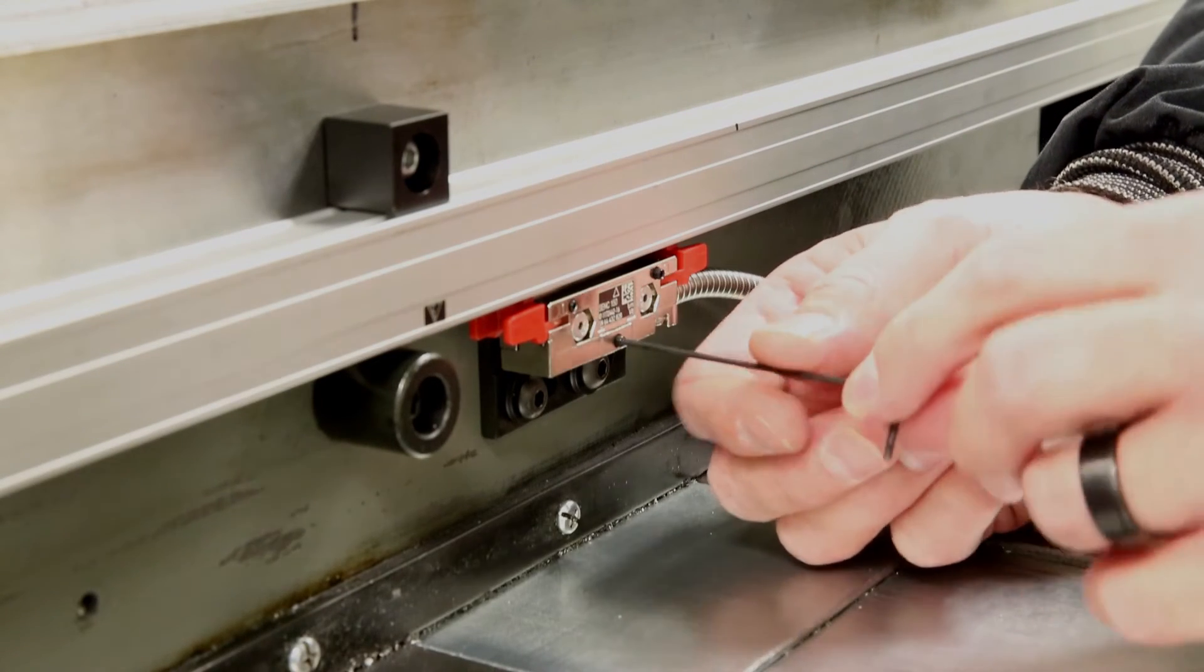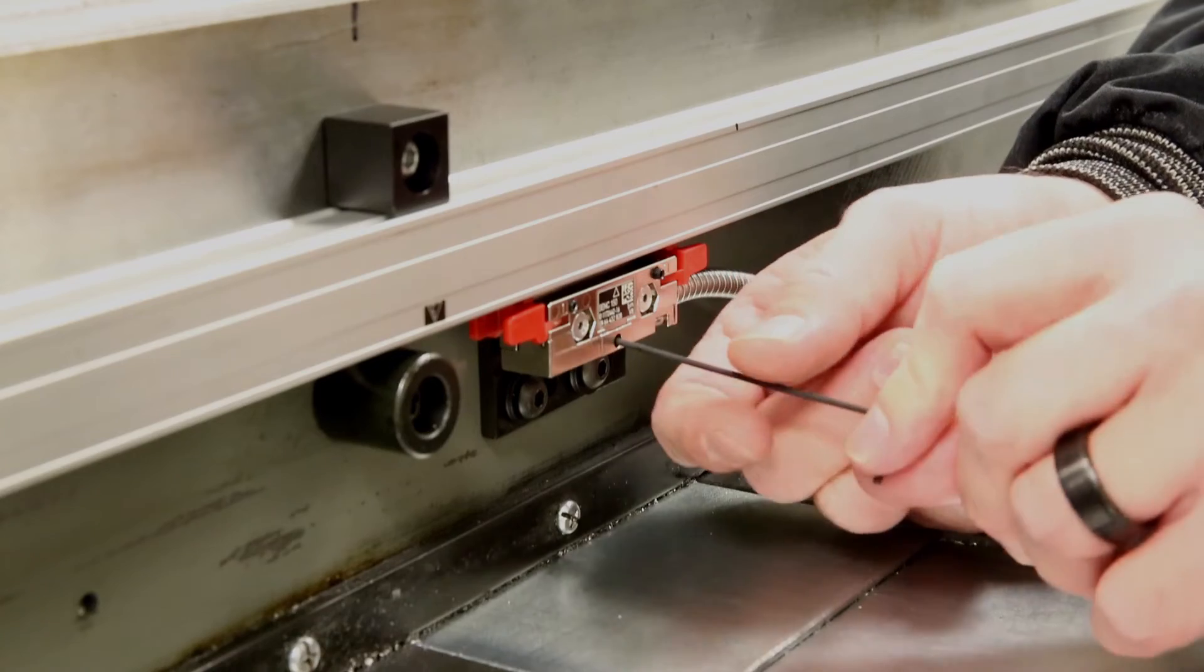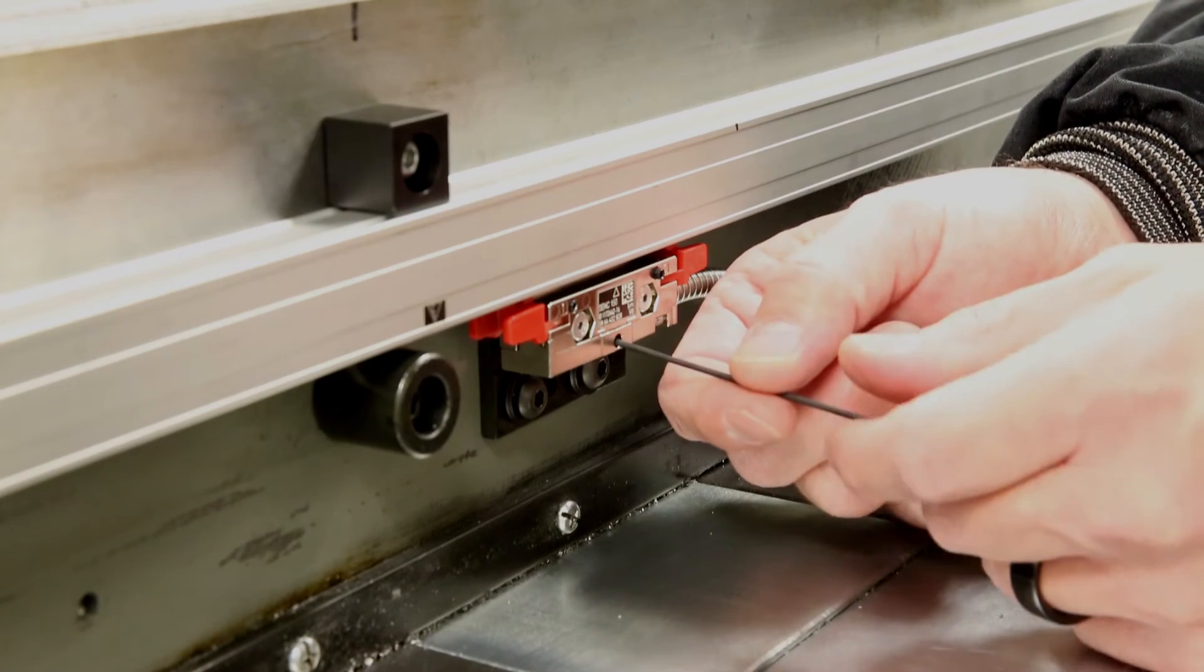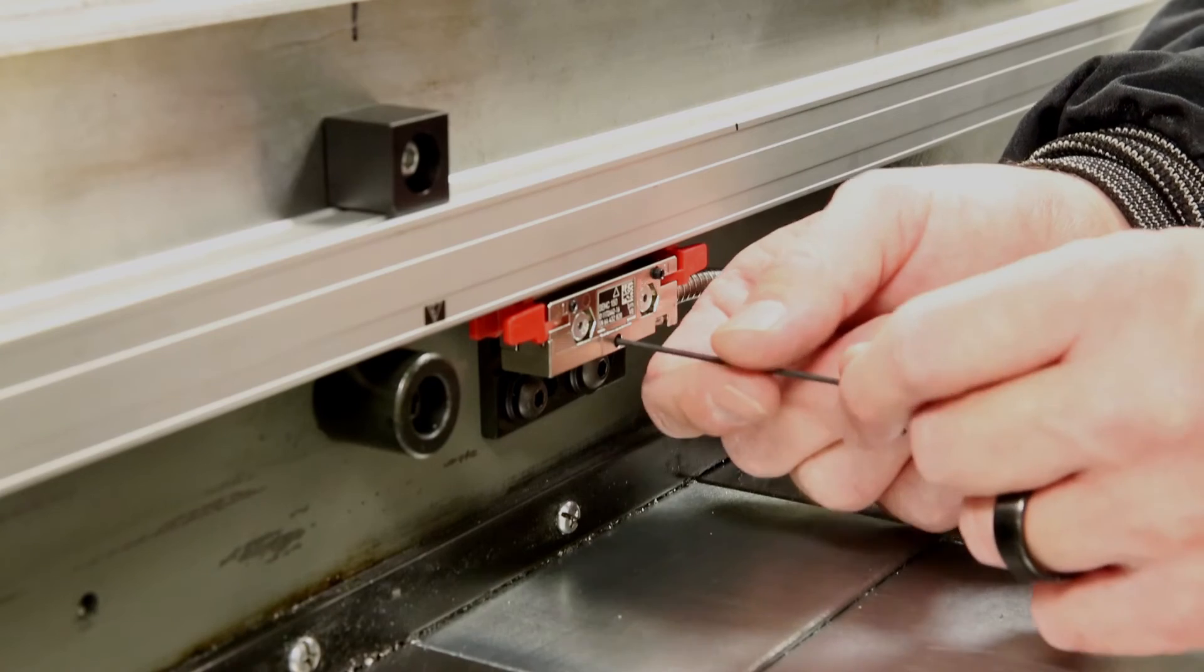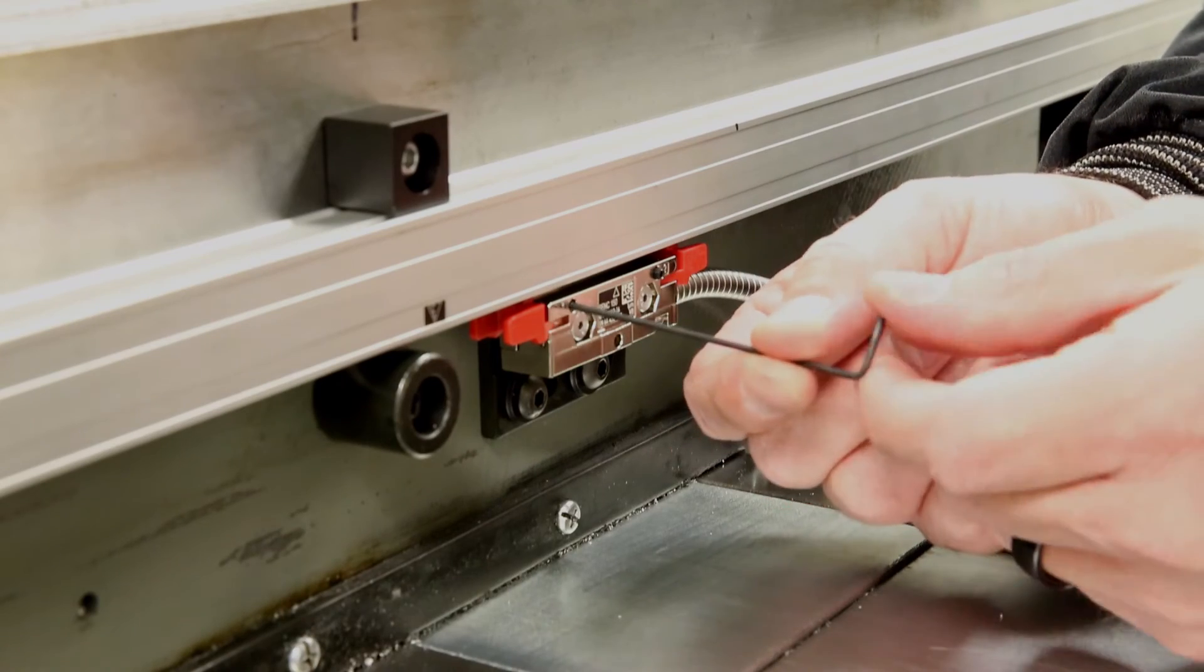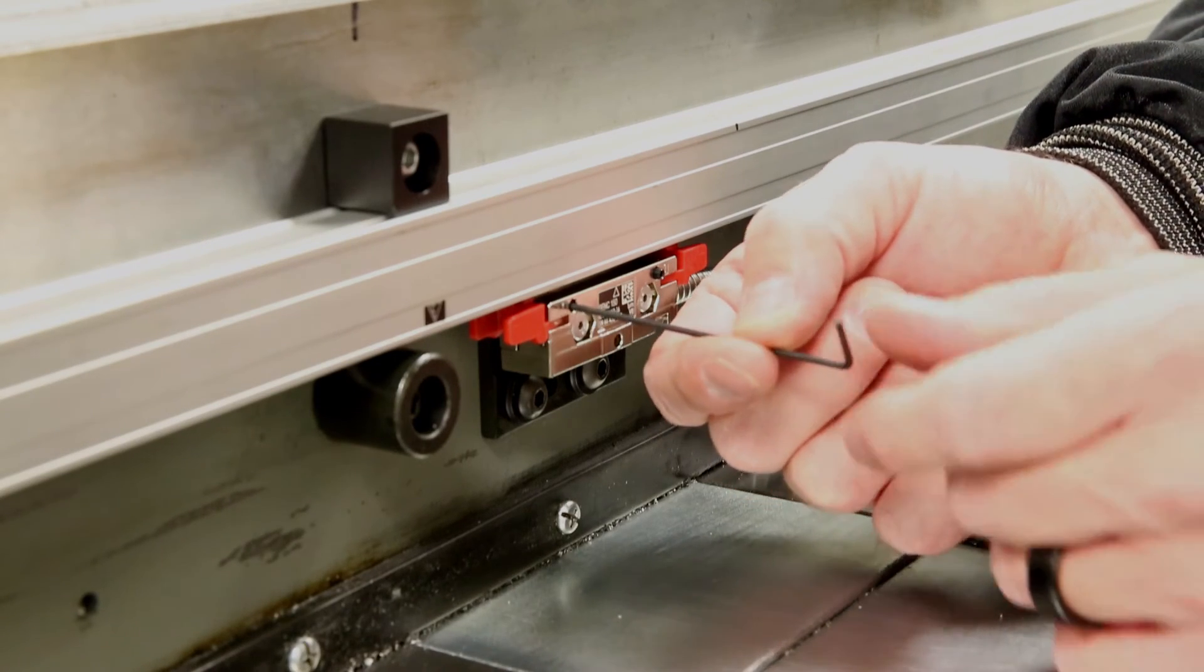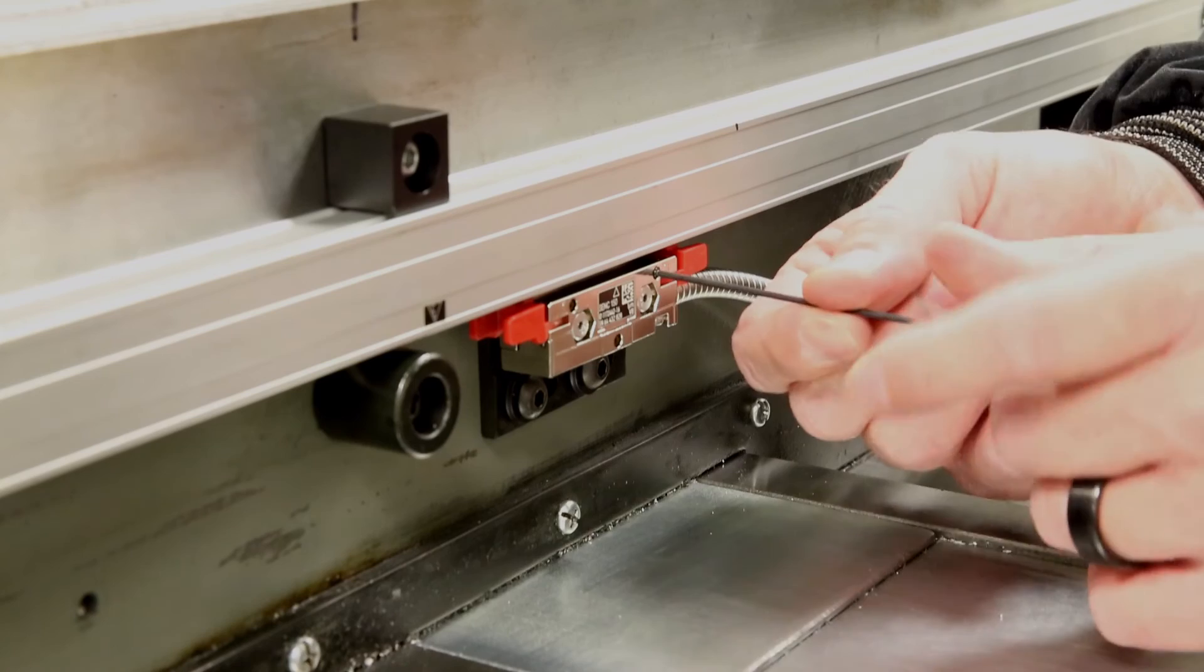Next, we're going to put the leveling screws through the reader head to just touch the bracket. Make sure not to tighten these. Just touch the bracket, and once it touches, remove the Allen key and do the two other screws.